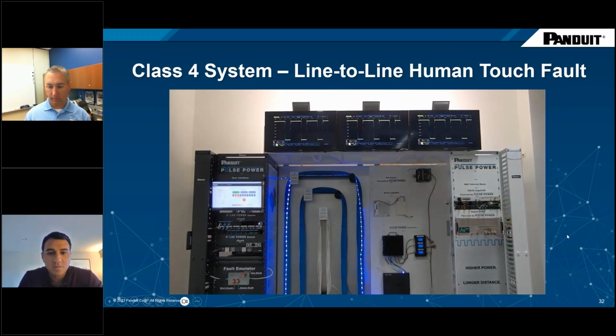I hope that was a helpful representation of how a system would behave when a line-to-line human touch happens, or when someone touches the cable. And just one thing to point out here, these systems will typically, after a fault, automatically turn back on if that fault doesn't exist anymore. If you compare that to the GFCI outlet you have in the bathroom or in the kitchen, you always have to go back and retest it to work again. These systems are smart enough that when the fault is not there, they'll turn back on automatically.